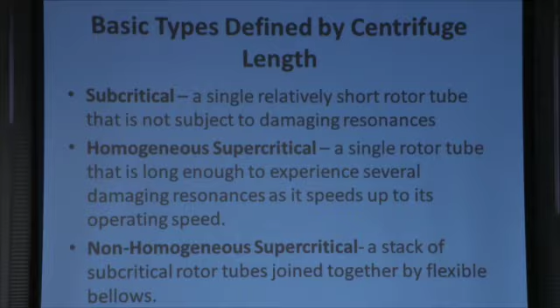And those occur with a solid spinning object, where at certain speeds or frequencies, when this rotor is spinning, if it has a certain length, then it hits a resonance that's actually going to make the rotor try to be like the shape of a banana. But if this is a solid object, you can imagine what's going to happen. If it bows out, it could hit the wall, it could break the bearings. And so you have to find a way to either avoid it, so these resonances you don't ever run into them, or to get through those resonances without having your centrifuge have its shape so distorted it breaks. And so subcritical means that you avoid the resonances. You just never hit them. And that has to do with making sure that the rotor tube is short enough so that when it spins up, it doesn't hit these critical, they're called flexural resonances.